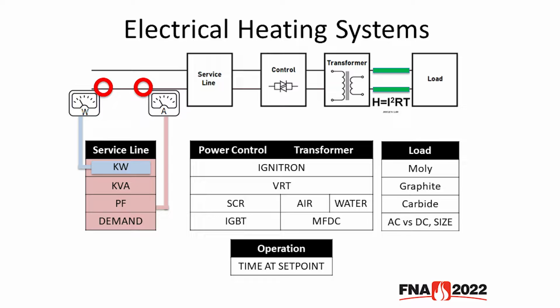Commonly used loads are graphite, molybdenum, or silicon carbide. An important variable at play in the load is also the type of current, AC or DC, and the physical size of the circuit. Finally, probably the most important variable here is time, which means how are you operating your furnace? Do you use it at 100% full tilt every time, or do you scale back to 50% power for long, slow runs? All of these variables can significantly impact the power quality of your furnace.